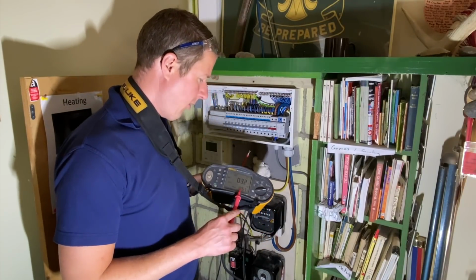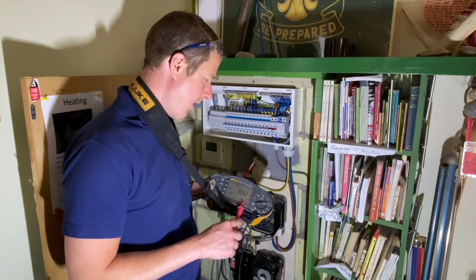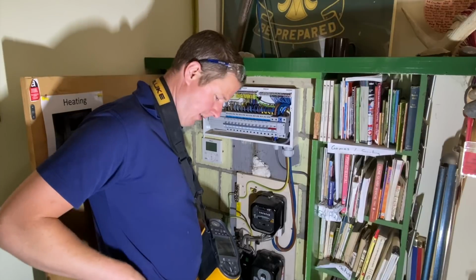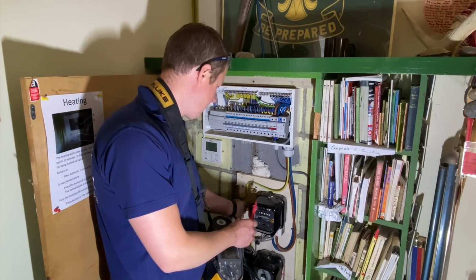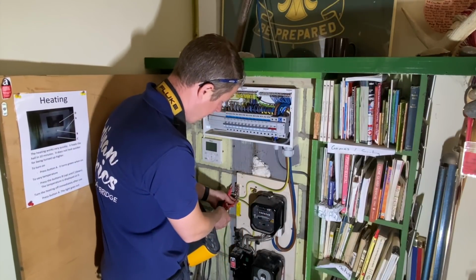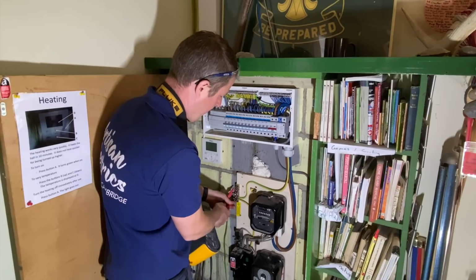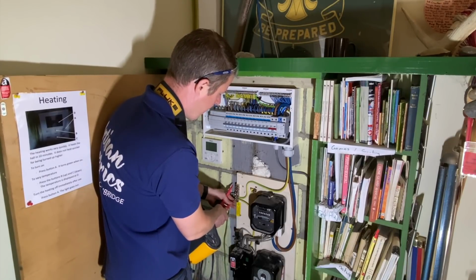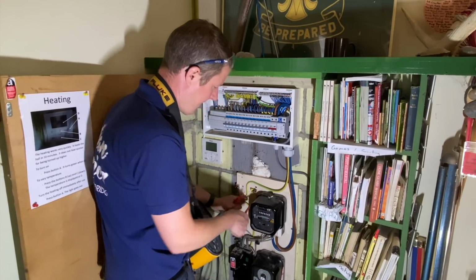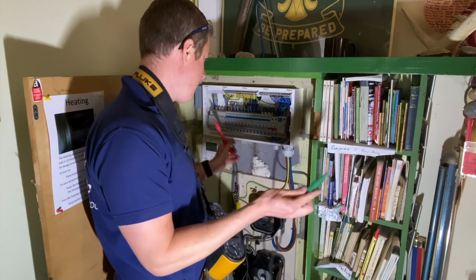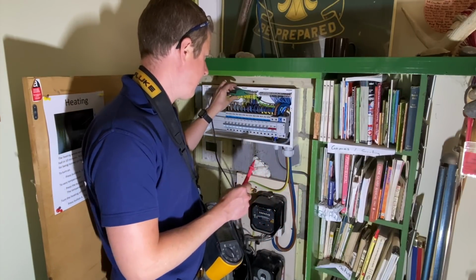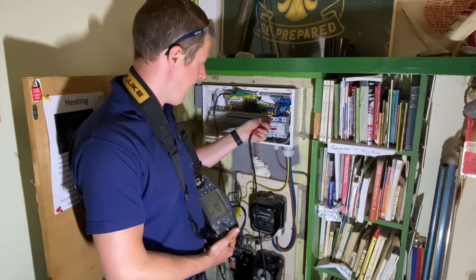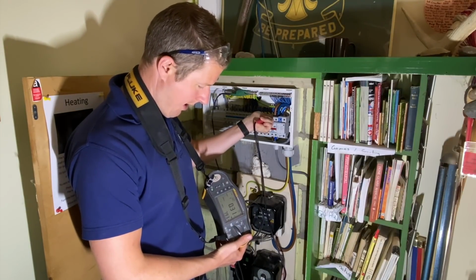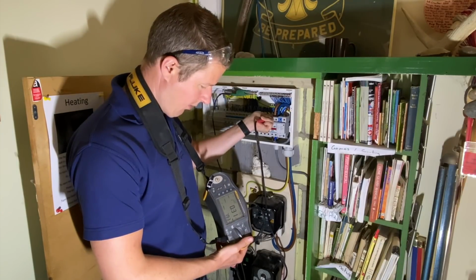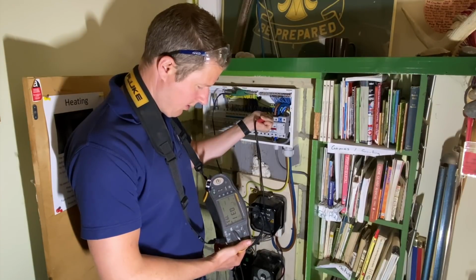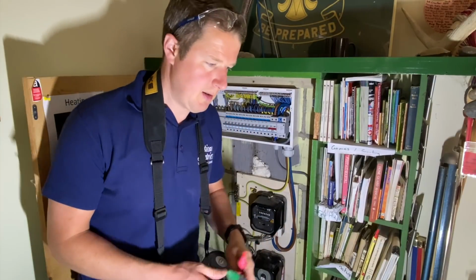Now we've got a prospective earth fault current reading of 767 amps as well. We have to take note of that because the next test we're going to do is our prospective fault current test, which will be carried out with the main earth conductor connected. External earth fault loop impedance, or Ze, is always carried out with all the main bonding conductors disconnected. In other words, we're just testing the supplier's earth. But PFC and PEFC, prospective fault current and prospective earth fault current, are always carried out with everything connected. So now I've got Zdb of 0.31 and PEFC of 793 amps, and then now I'm going to do a PFC.